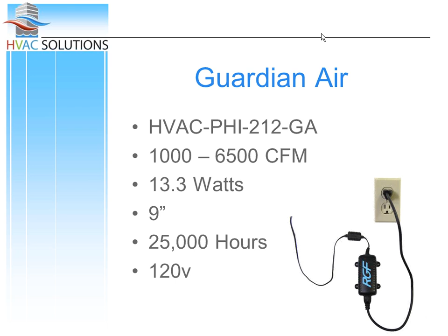So the unit we use 9 out of 10 times is called the 212GA. This unit is good for systems up to 6,500 CFM. It doesn't use a lot of power - it's kind of like a night light. It is 9 inches long, and the cell is going to last 25,000 hours. That's basically 3 years, and then you have to replace that cell. This unit comes with a plug, so you can plug it in and take 115, 120 volts, or you could cut the plug and send 220 right to it. It has an automatic switching transformer that will accept anything from 115 to 220. If you need 24 volts, we do offer that unit, but we do not stock it - it is a separate unit.